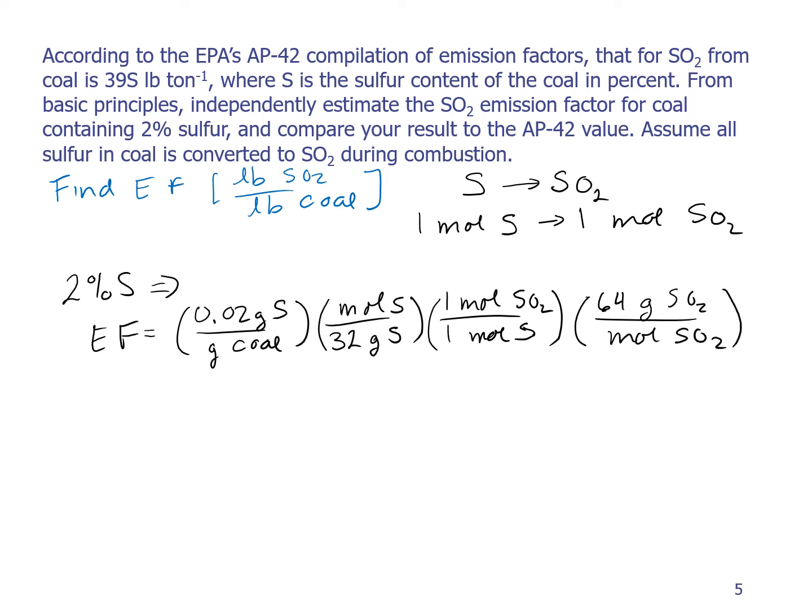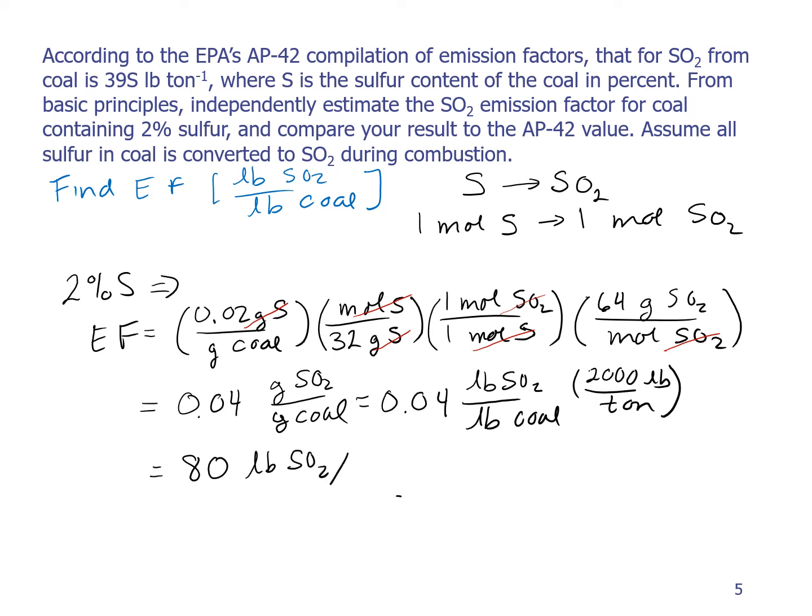Notice that my units here cancel. I go from grams of sulfur to moles of sulfur to moles of SO2, and finally I end up with grams of SO2. And so this gives me 0.04 grams of SO2 per gram of coal. Now the emission factor in AP-42 is actually pounds per ton. So this is grams per gram, so it's going to be the same as pounds per pound. So this is 0.04 pounds of SO2 per pound of coal. Now I can use a conversion factor to get from pounds to tons. So I want to multiply by 2,000 pounds per ton. That's for the coal. And I get 80 pounds of SO2 per ton of coal.